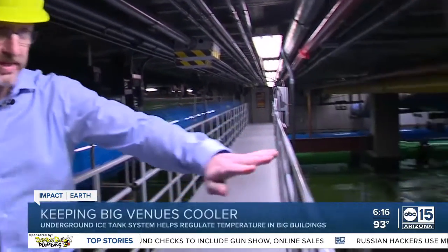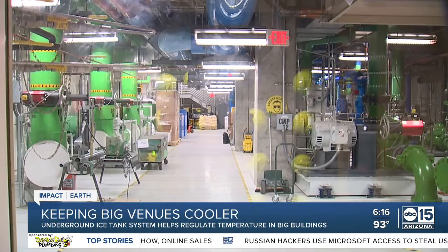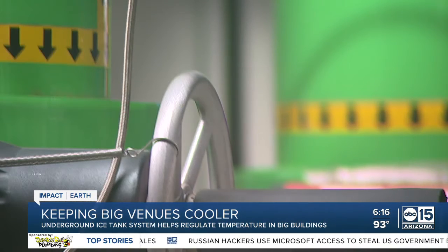The ice tank is basically a thermal storage facility. Inside the ice tanks, there are three channels of water where it flows from one side to the other using potable water. It goes from the plant through a heat exchanger at the customer and then comes back. This water doesn't evaporate — there's no loss unless there's a leak, which is why they dye the water green.